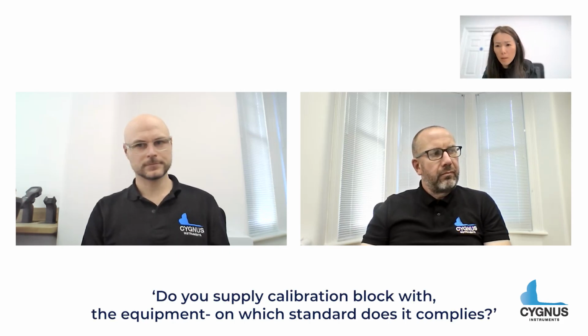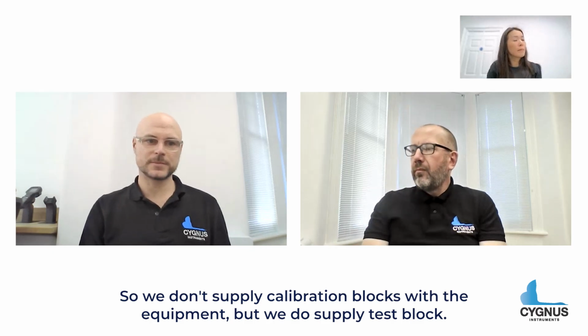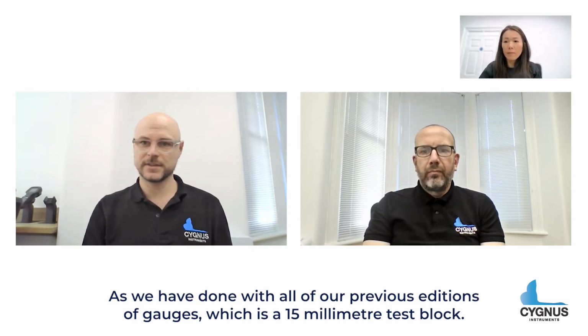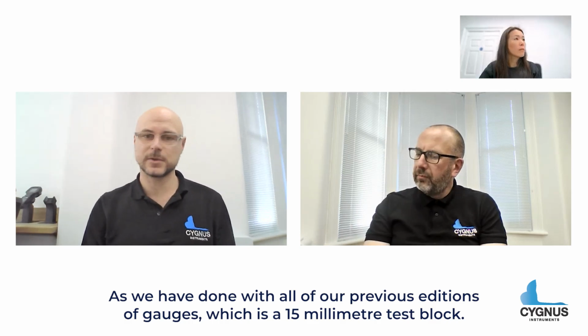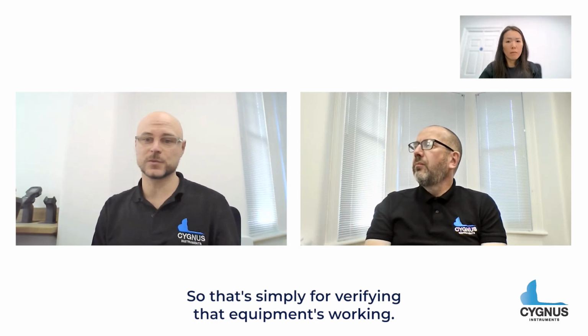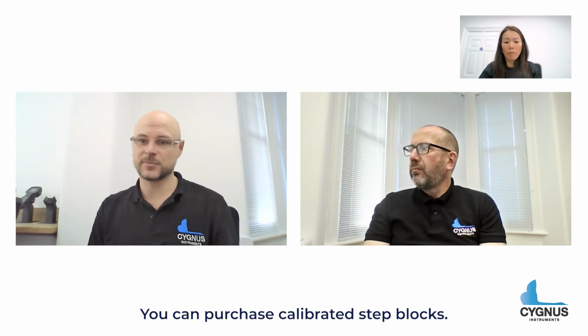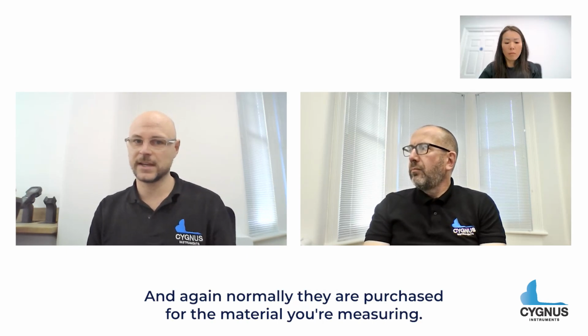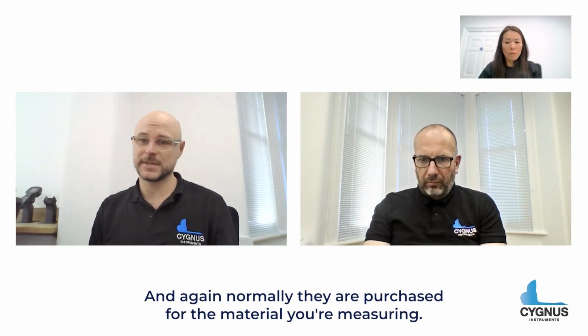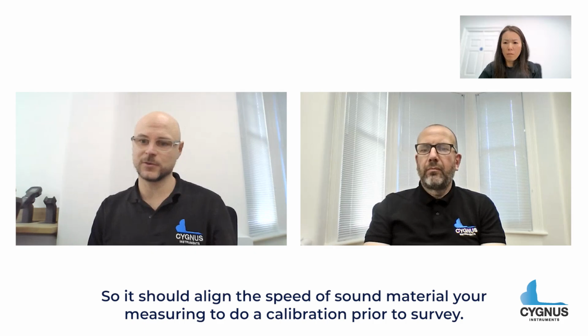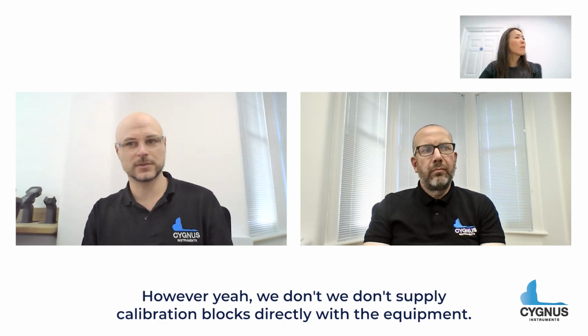Okay, thank you, Simon. Next question for calibration. Do you supply calibration block with the equipment? Which standard does it comply with? Matt, could you help with that? So we don't supply a calibration block with the equipment. We do supply a test block, as we have done with all of our previous editions of gauges, which is a 15mm test block. So that's simply for verifying the equipment's working. You can purchase calibrated step blocks, and again, normally they are purchased for the material that you're measuring, so it should align with that speed of sound of the material you're measuring to do a calibration prior to survey. However, we don't supply calibration blocks directly with the equipment.